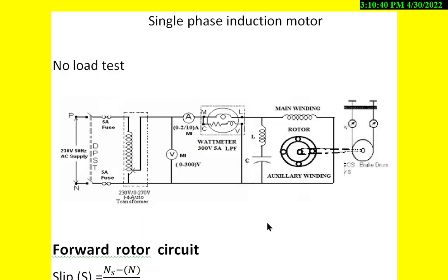This is the general connection for the single phase induction motor to conduct the no load test and the blocked rotor test. Under no load condition, the ammeter range is 0 to 2 amperes and the voltmeter rating is 0 to 300 volts, and the wattmeter is an LPF wattmeter with voltage coil rating 300 volts and current coil rating 5 amperes, and we keep this belt loose, meaning the spring balances S1 and S2 show 0 reading.